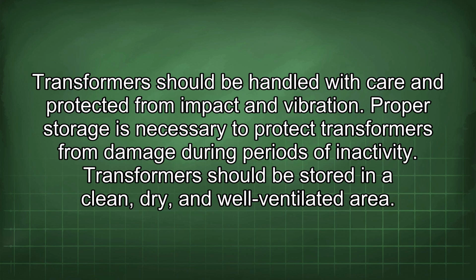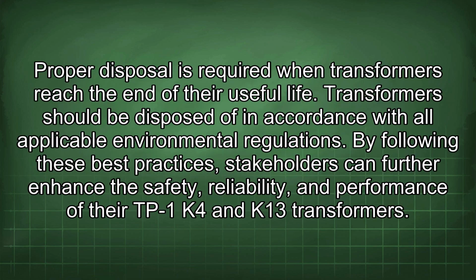Proper storage is necessary to protect transformers from damage during periods of inactivity. Transformers should be stored in a clean, dry, and well-ventilated area. Proper disposal is required when transformers reach the end of their useful life. Transformers should be disposed of in accordance with all applicable environmental regulations.